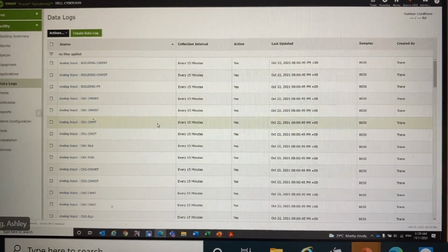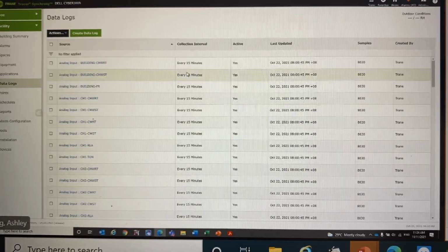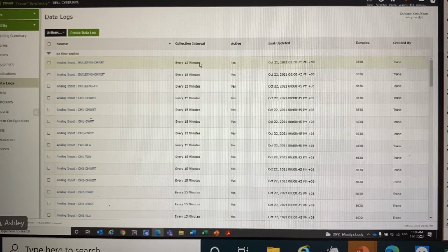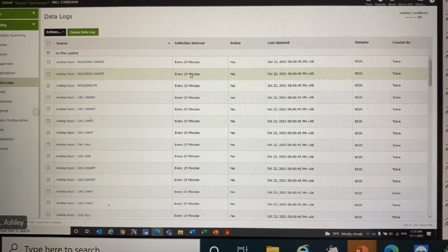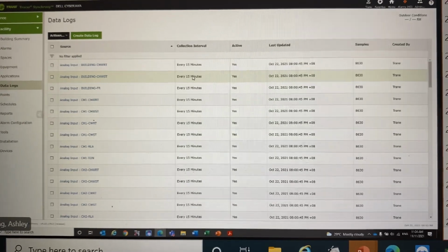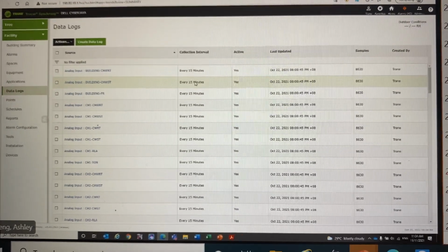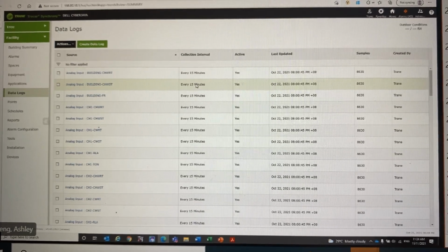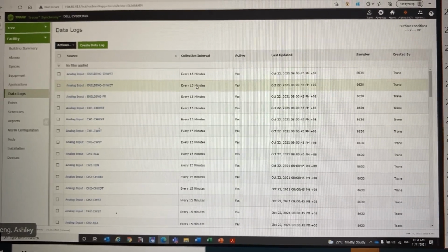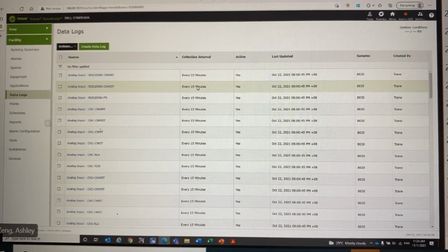For points where we collect data logs at intervals of 1 minute, we do not recommend SE to store it for more than 7 days. In Singapore, we are more conservative. Usually we only store 1 minute data for points for 3 days or 5 days, with a maximum of 7 days.